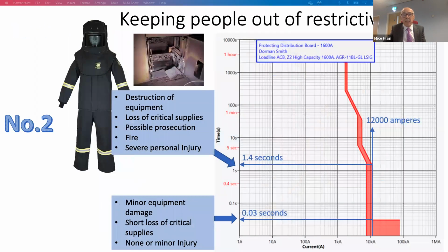I'm not anti-PPE, by the way, not in any shape or form. I just think that where we can reduce the incident energy levels, we should be doing, and that's basically what this is all about. But the difference between restrictive PPE and no PPE at all is often just a few amps, and this is what I'm trying to put over in this particular graph on the right-hand side. This is a 1600 amp circuit breaker, Dorman Smith Loadline air circuit breaker.